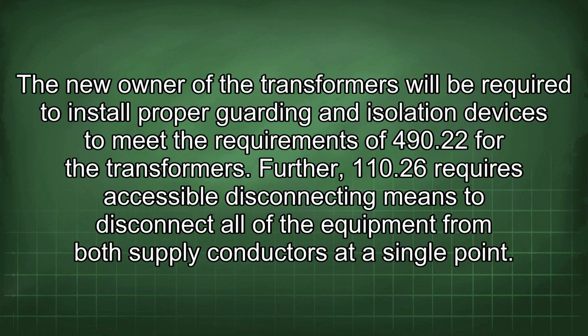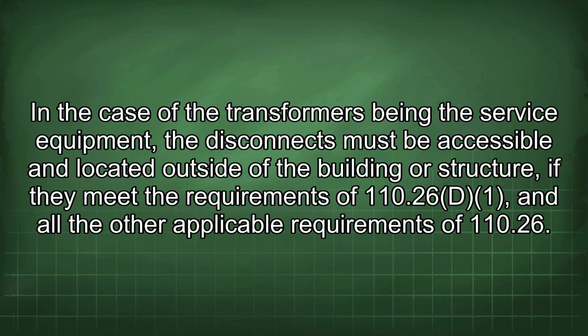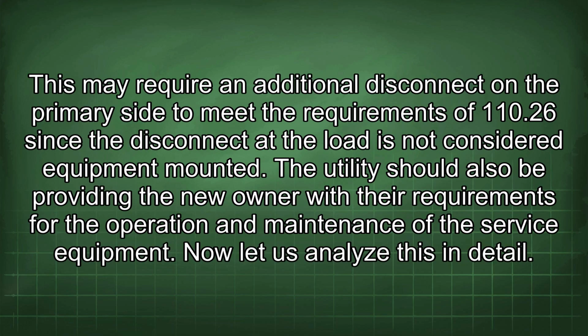The new owner of the transformers will be required to install proper guarding and isolation devices to meet the requirements of 490.22 for the transformers. Further, 110.26 requires accessible disconnecting means to disconnect all of the equipment from both supply conductors at a single point. In the case of the transformers being the service equipment, the disconnects must be accessible and located outside of the building or structure if they meet the requirements of 110.26(D)(1) and all the other applicable requirements of 110.26. This may require an additional disconnect on the primary side to meet the requirements of 110.26 since the disconnect at the load is not considered equipment mounted. The utility should also be providing the new owner with their requirements for the operation and maintenance of the service equipment. Now let us analyze this in detail.